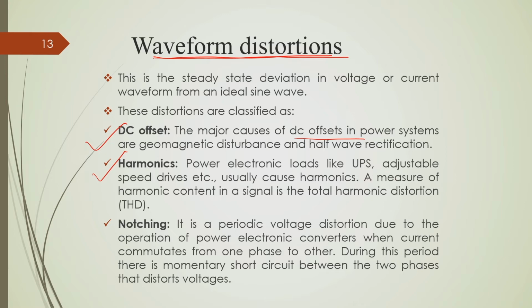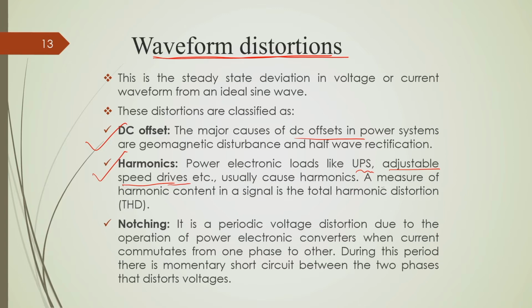And harmonics are generated because of UPS, adjustable speed drives, all of which are basically power electronics based loads, or power electronics based equipment, and they cause harmonics and transmit harmonics to the system. Okay. If there is harmonic present in the load, this will be transmitted to the whole network as well, which will cause distortion in the supply voltage. Similarly, notching is another periodic voltage distortion due to the operation of power electronics converters when current commutates from one phase to another.